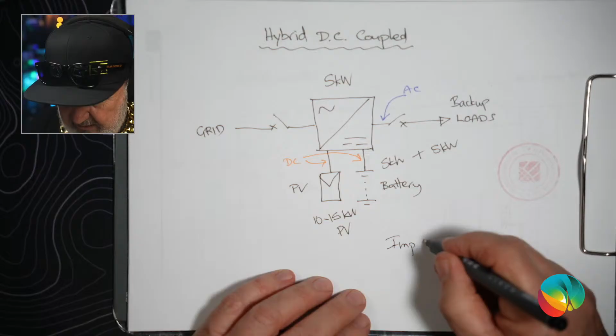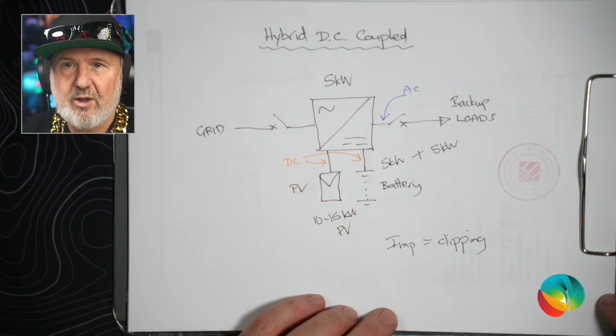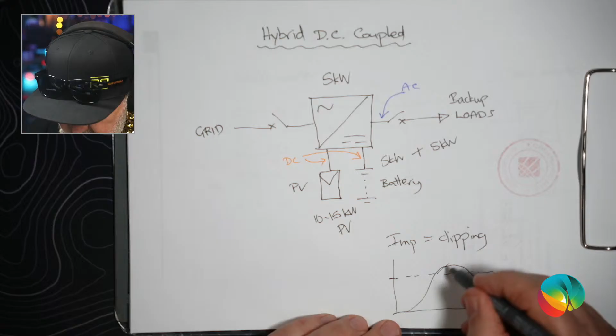The IMP, which is current at maximum power, actually is the point at which clipping occurs. It's not a point at which you must not go beyond. So if you're drawing a little production curve here, if you look at solar, it often looks like a bell curve like this. If the IMP is here, what's going to happen is that bit never gets produced. We just end up with a flat topped production curve, and that's the clipping that occurs.